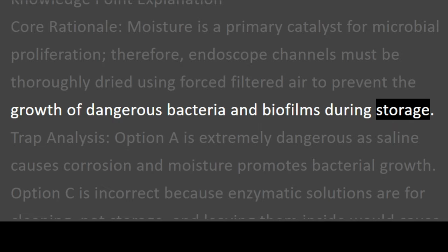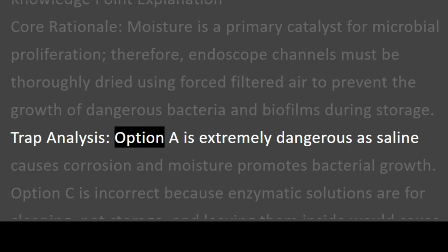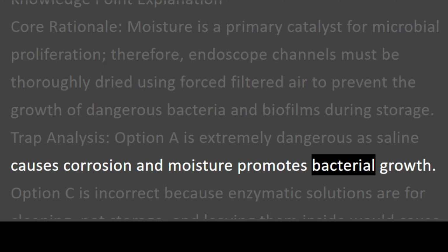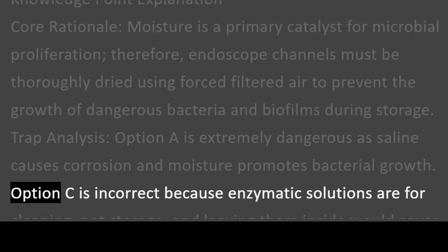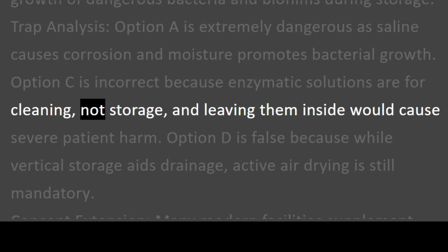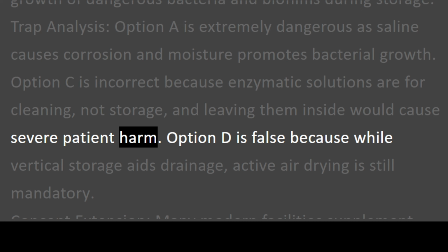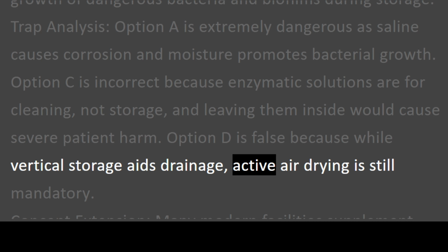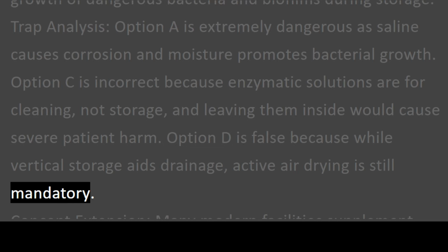Trap analysis: option A is extremely dangerous as saline causes corrosion and moisture promotes bacterial growth. Option C is incorrect because enzymatic solutions are for cleaning, not storage, and leaving them inside would cause severe patient harm. Option D is false because while vertical storage aids drainage, active air drying is still mandatory.